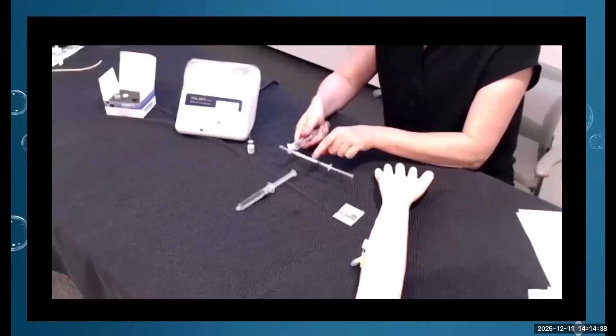Take the needle out of the vial, remove the needle cap from the syringe, and place it on your 3-way stopcock, making sure there are no bubbles within the solution. You can gently tap the solution to remove the bubbles or air from the tubing. Then take your saline syringe and attach it 90 degrees to your contrast and to your extension tubing. Notice here the off position is facing the saline syringe. Clean your IV line, and then gently turn the 3-way stopcock into the IV line, being very careful not to twist the tubing. Make sure you open the clamp.